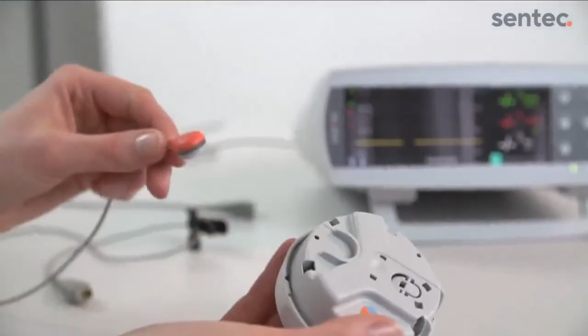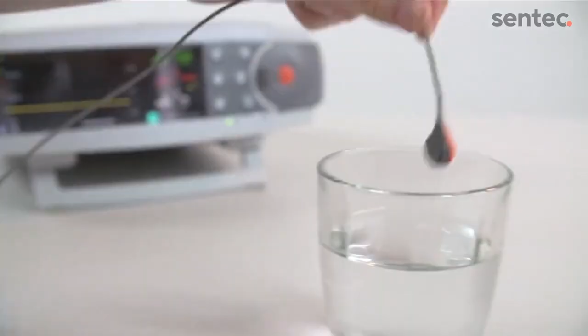Follow the next steps for a clean and soak. First, remove the old membrane from the sensor using the bottom part of the membrane changer. If the membrane does not come off easily, you can first soak the sensor with the membrane on. Once the membrane is removed, immerse the sensor into clean room temperature water for 3 minutes.